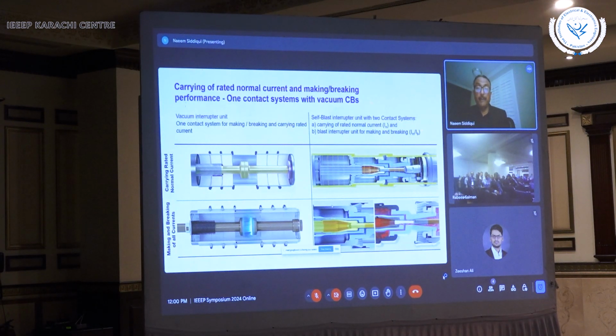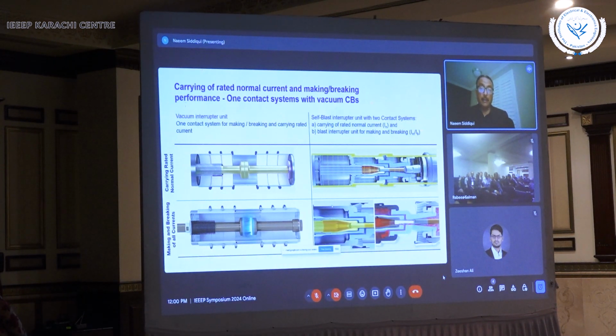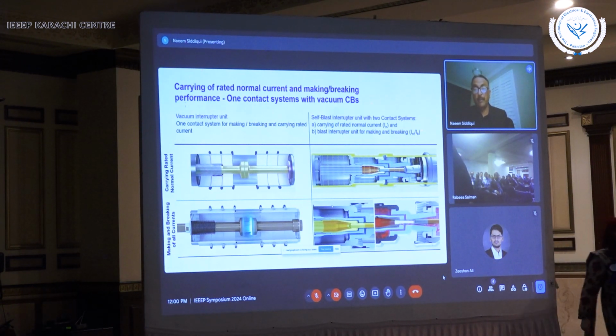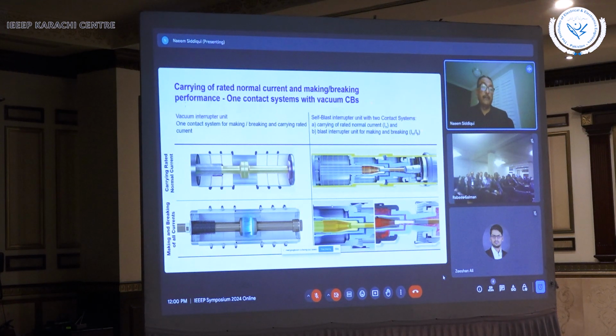On the right side, you can see the SF6, where we have basically a very complex contact systems, main contact and the pin contact, and at the time of current breaking, you have very long arc, very long basically arc energy, we call it arc energy in terms of basically breaking the current at 40 kA or 63 kA, very high heat basically source that can produce inside of the breaker. Whereas in vacuum tube, you can see on the left side that we have very small distance, and it's kind of like a snap action. It can basically make or break type thing.